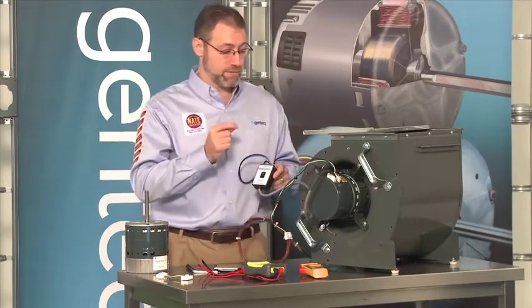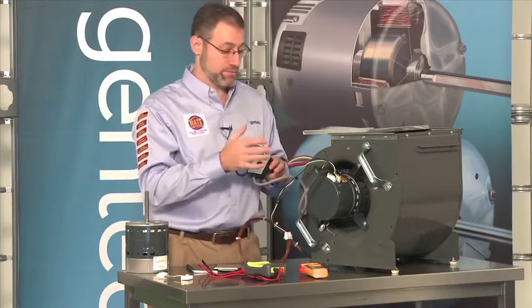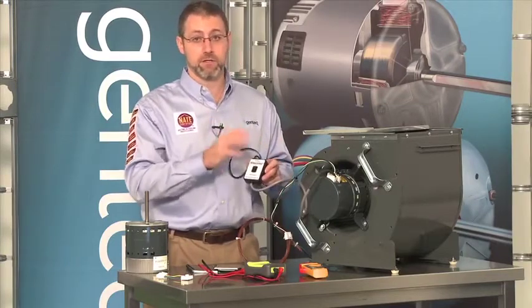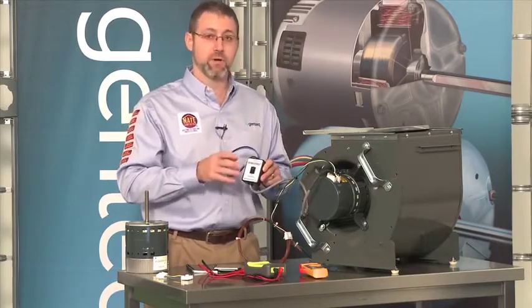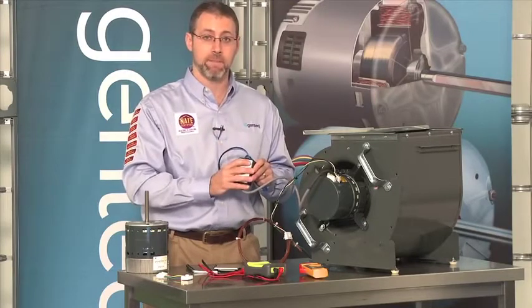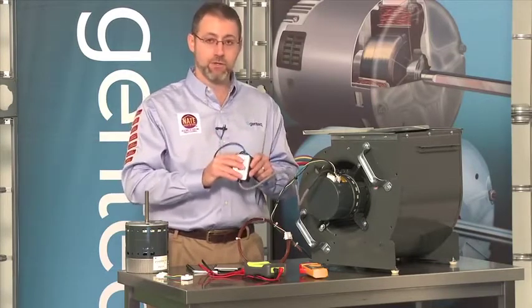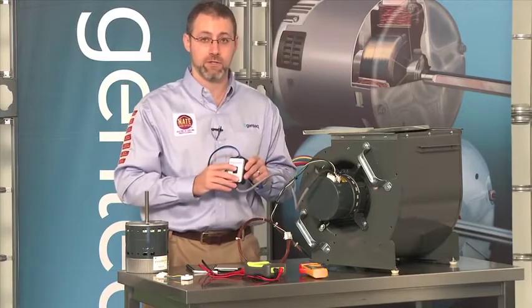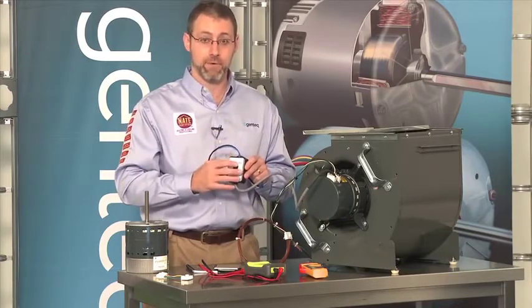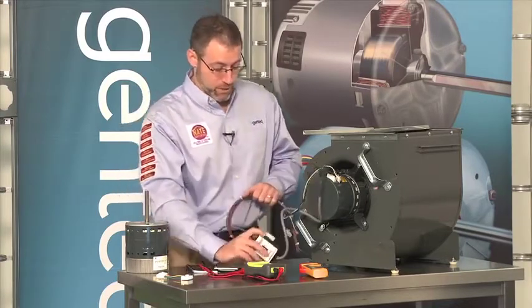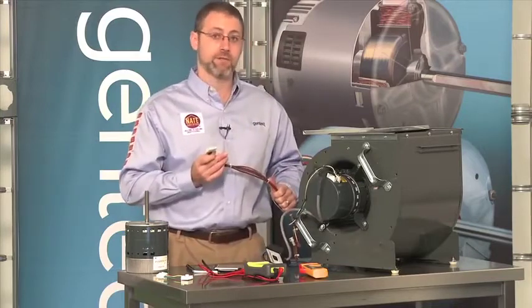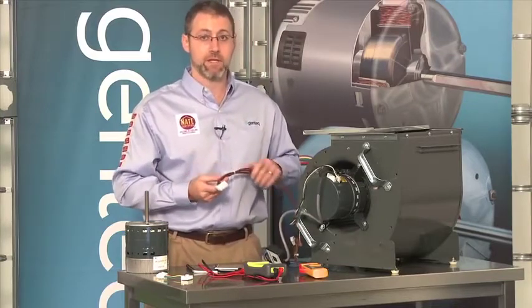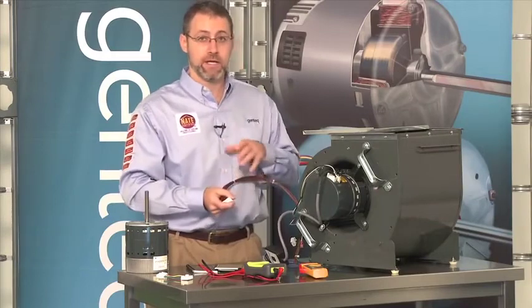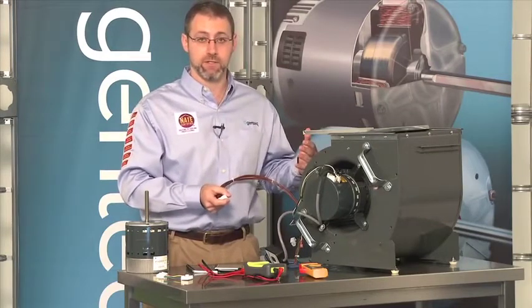Now, obviously, if the motor does not run, there's something wrong with the motor. But let's look at another scenario first. Let's say the motor does run with the TechMate. That means that with our tool sending a known communication signal, the motor operates, but with the OEM wiring harness, the motor does not operate. So that means the problem is not with the motor, it's back in the HVAC system.